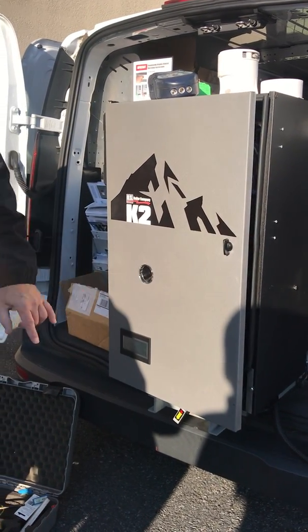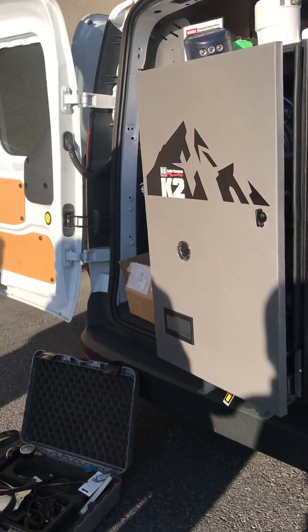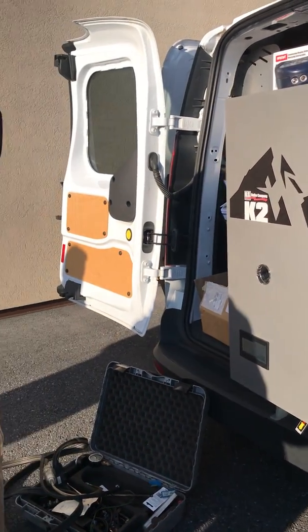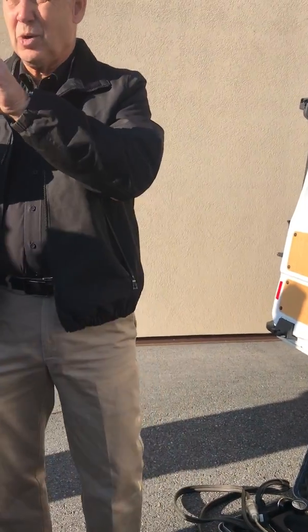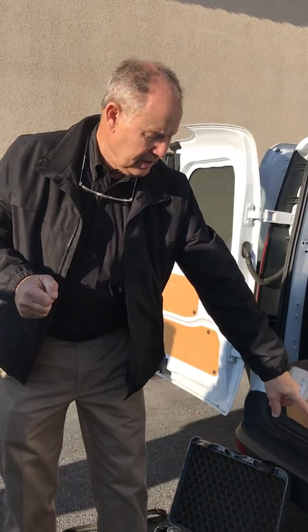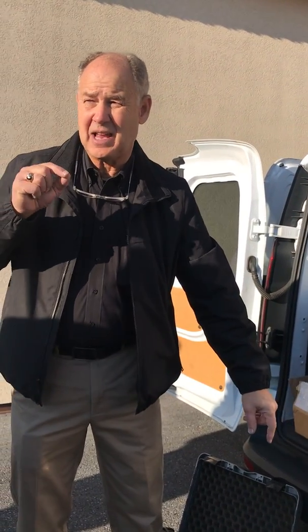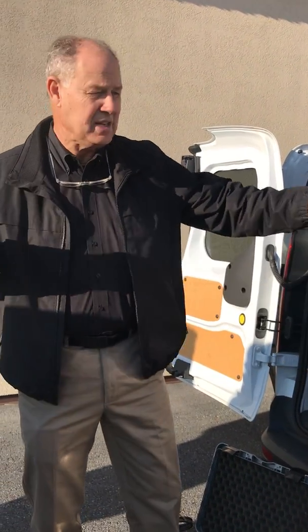And it actually, right now it says standby. But when it goes to light, you hit that status, it goes through pre-ignition. It'll do a pre-check for the controls, and then it finally gets the direct ignition. That's when you get your spark. That's when you're going to get your gas valve open, under direct ignition. So if you ever are servicing one of those, and we'll show you upstairs, you just hit that status, so you can see exactly what stage it's in.